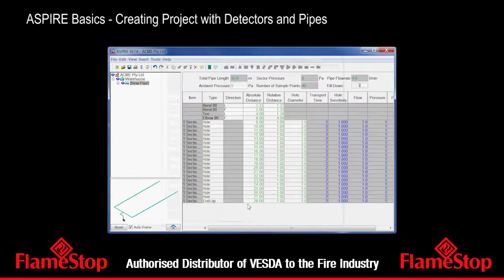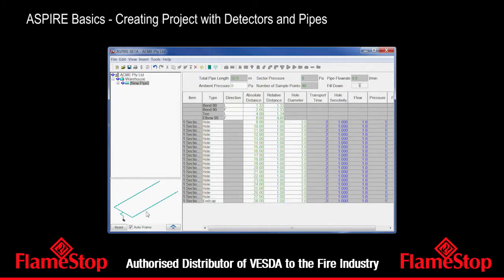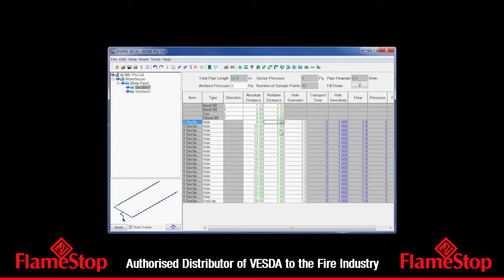If we're using capillaries, we can go into those fields as well. The ambient pressure setting is really for the case where your pipe network is in a different room with a pressure differential from where the detector is. Leave it like that. Here we can see all our holes. You'll notice in the view we've got our pipe network with all the holes along it. Now, if we decide we need bigger spacing between holes — instead of one metre, let's go to two metres — we can go and edit this cell here.